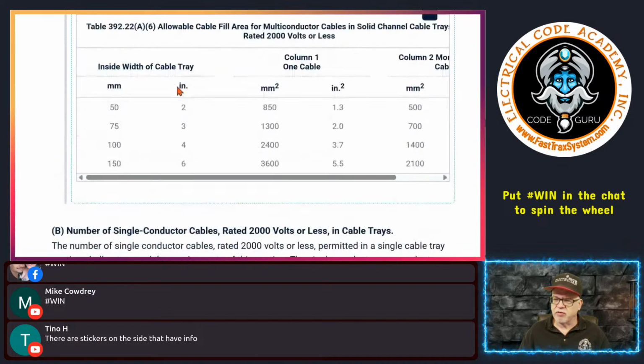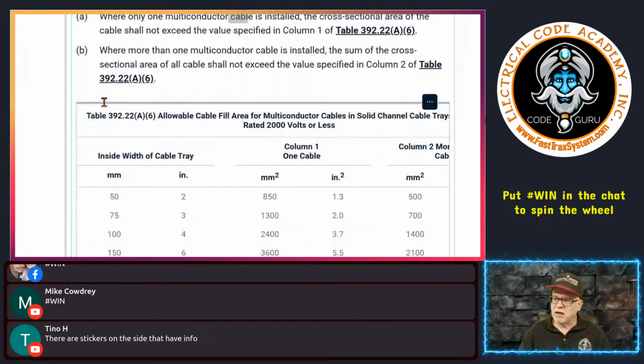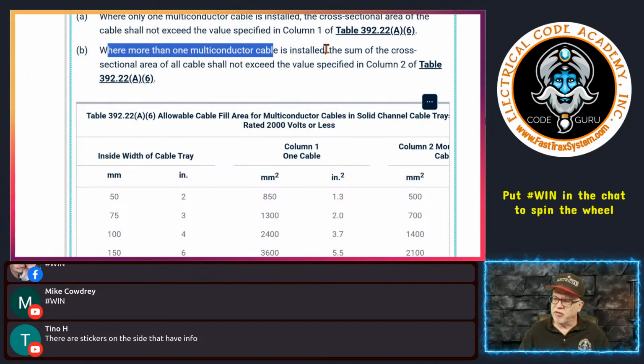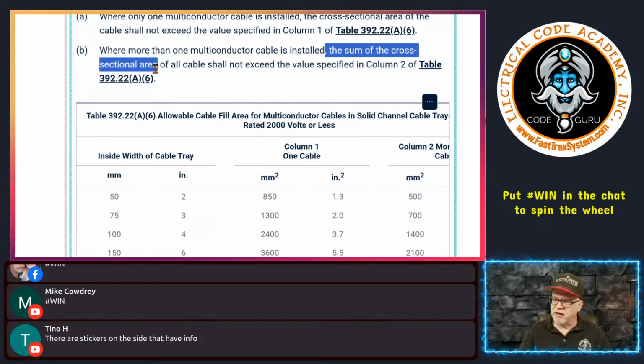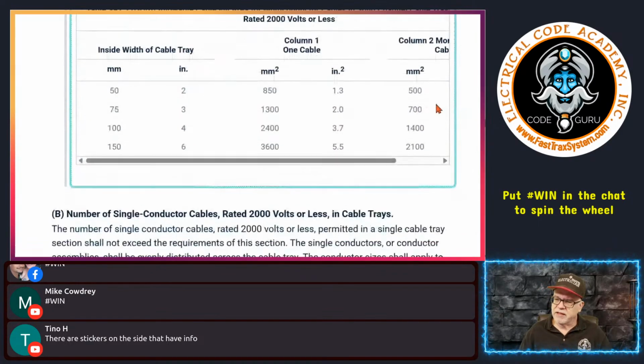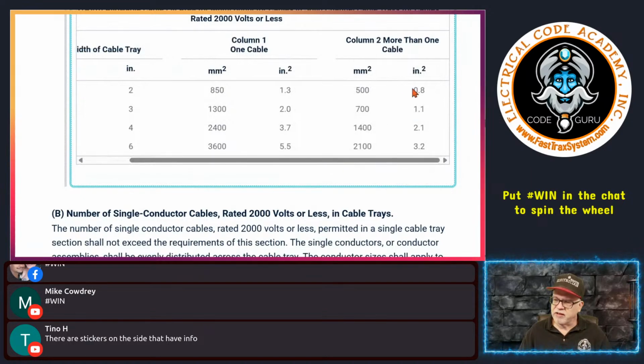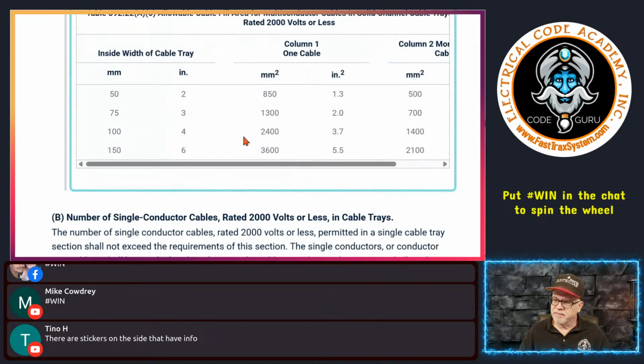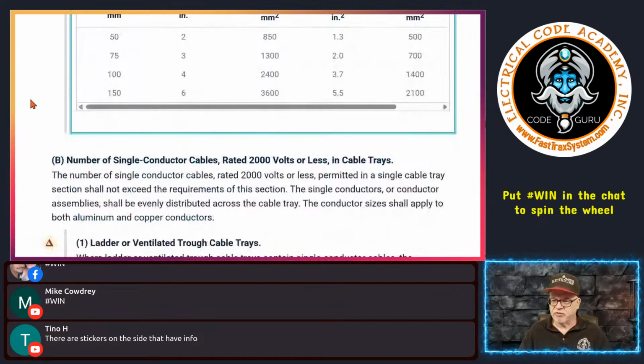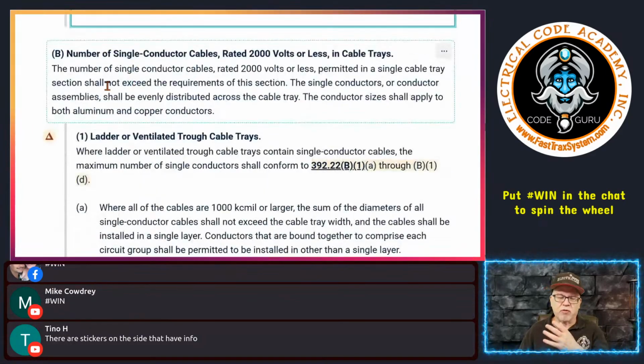And then, of course, in this one, it says where more than one multi-conductor cable is installed, the sum of the cross-sectional area of all the cables. And when you see sum, it just means adding them up, however many you have. Adding their cross-sectional areas up, and they cannot exceed the values in column 2. And here you see, again, as we said, here's the values in column 2. Okay, pretty straightforward. And we talked about this, so remember everything that we talked about.